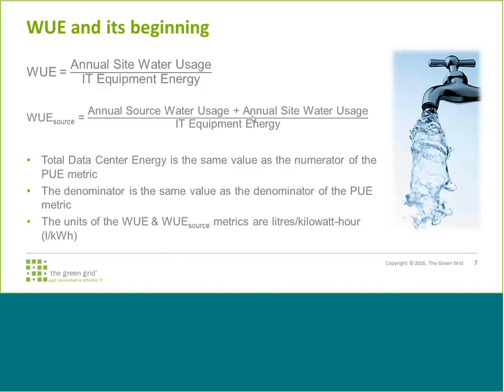Here the goal is to get as close to zero as possible. I'll speak to CUE for a second: currently, those using 100% renewable energy around the clock, and not ever running their diesel generators, can make a case for having a CUE of 0. The reality is, as soon as you fire up your diesel generator, you have some amount of carbon emissions, so you're close to 0, but not quite 0. Similarly with WUE, the goal is to get to 0. Well, if you have chillers and use chilled water systems, which many of us around the world are, it's very hard to get there, but there are steps you can take to drive it down. When we're looking at source water usage and annual site water usage, we're moving further upstream.